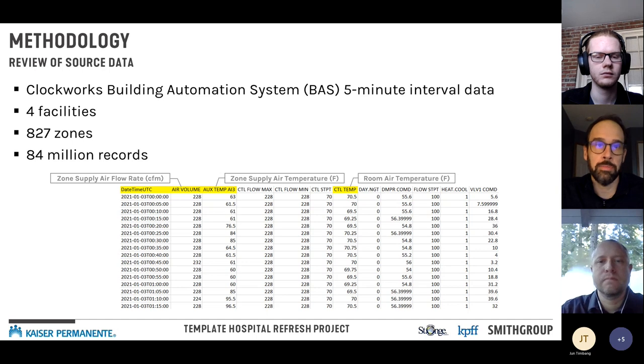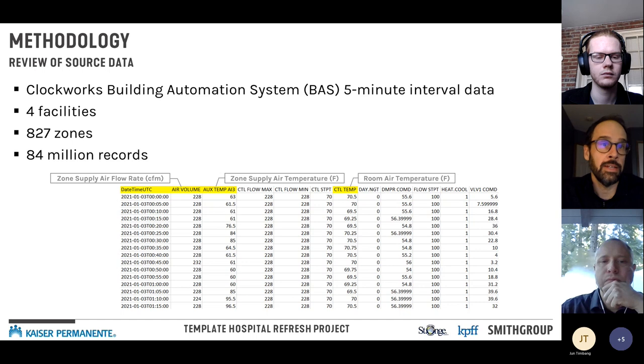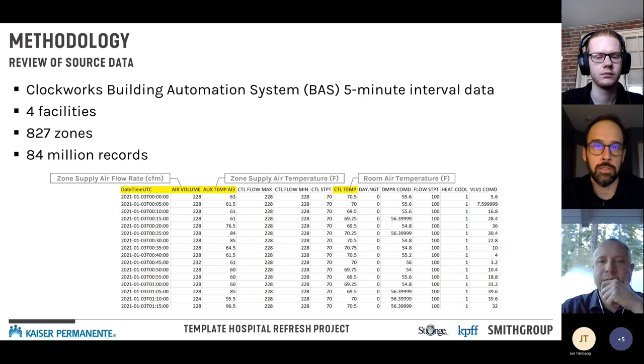The CSV data has key columns: a timestamp field at every five minutes for the year — 2020 was the primary period of analysis — along with the zone supply airflow rate, zone air temperature, and room air temperature. Those three columns are used to derive the load calculation.